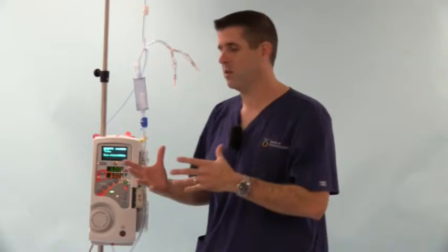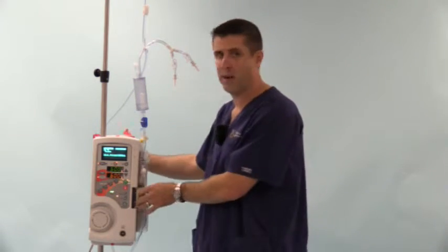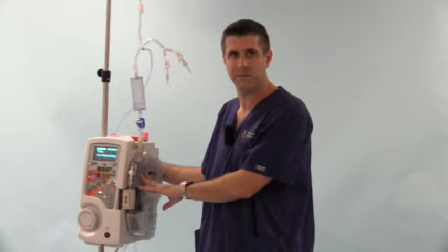Number one, air in the patient line. Our system uses a unique active air removal technology that is the most efficient on the market. And it works very effectively at very high flow rates and at low flow rates. That greatly minimizes the chance that you'll ever have air into the patient line from the cassette. We also have 4 air sensors, so we've got a lot of redundancy built in to ensure patient safety.